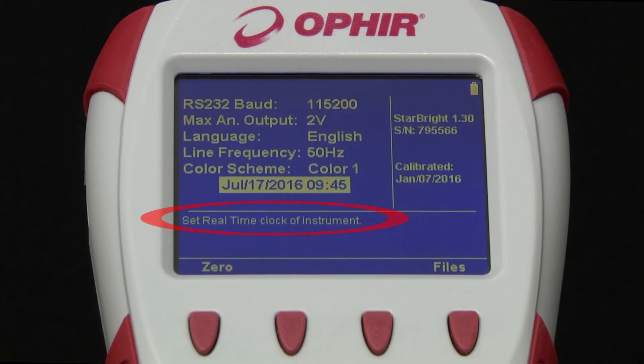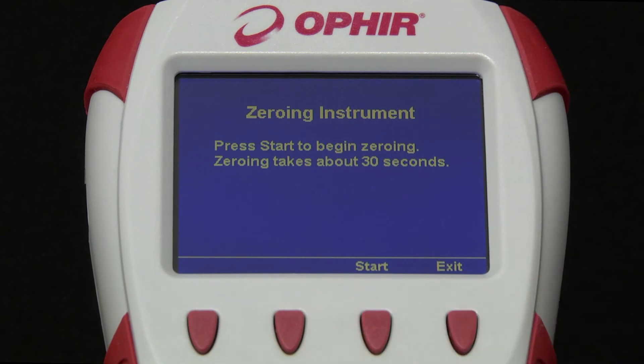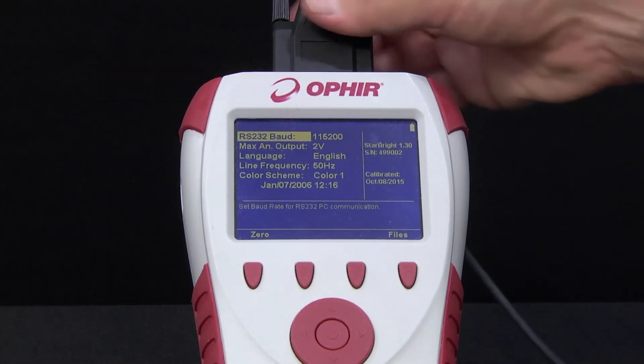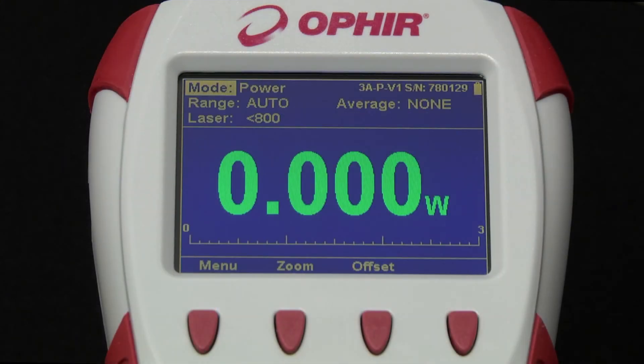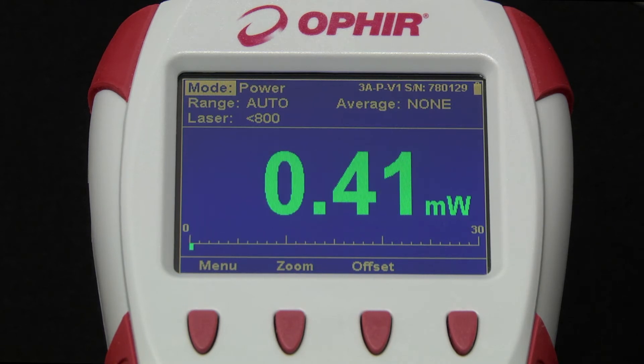Note the short explanatory text for each setting. We can also zero the instrument, which we recommend doing periodically — every other month or so — to zero out electrical biases that sometimes build up. When we now connect a sensor, note how the StarBright automatically restarts as it reads the sensor's calibration and related data stored in the sensor's EEPROM.